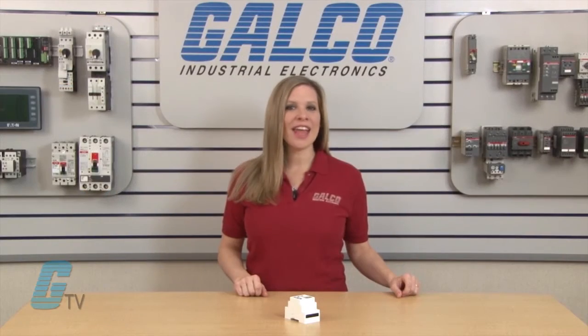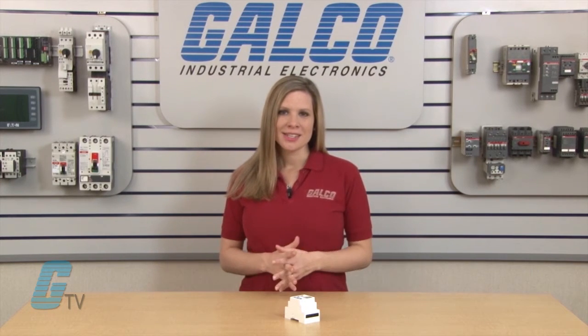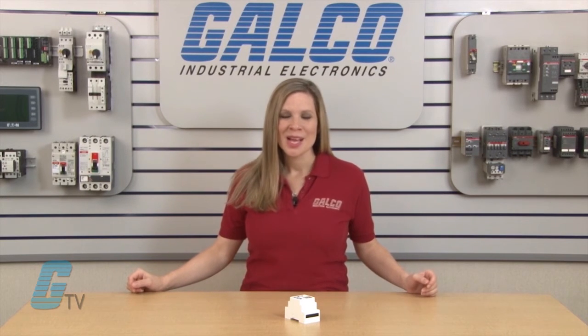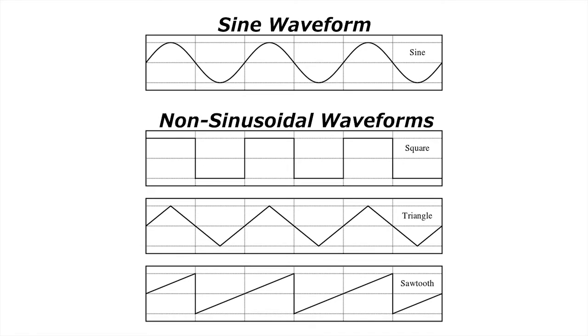Their innovative analog-to-digital sensing circuitry allows for true full-wave monitoring of all three phases, delivering the highest level of protection possible. True RMS voltage measurement ensures accurate sensing in most generator and other applications with non-sinusoidal waveforms, which eliminates nuisance tripping.